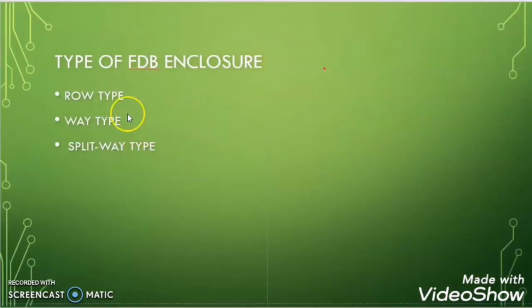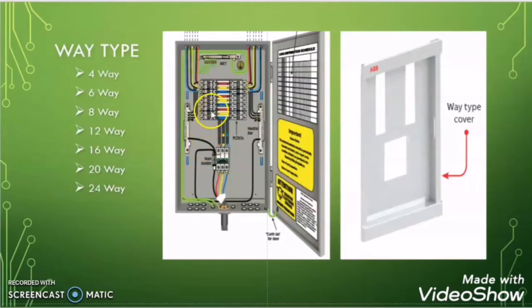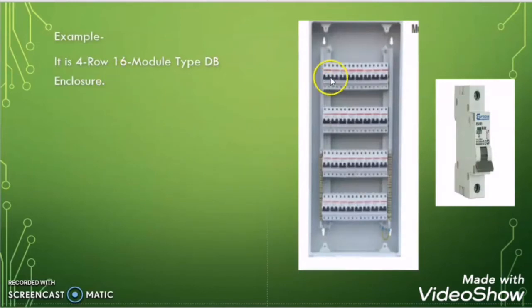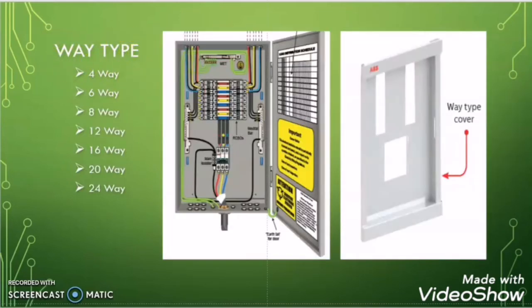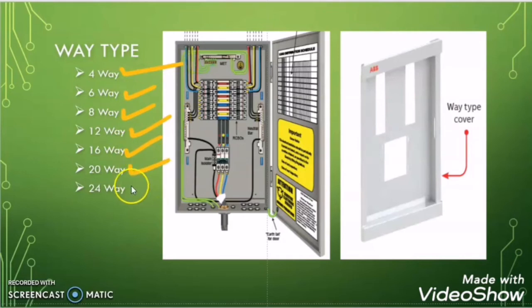Now let us discuss about the second type of FDB enclosure — the way type FDB enclosure. In way type FDB enclosure, the breakers are arranged inside the panel in a vertical pattern. The way type breaker can be of 4 way, 6 way, 8 way, 12 way, 16 way, 20 way, or 24 way type.